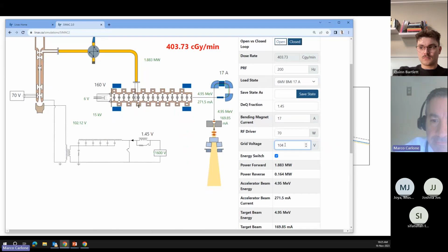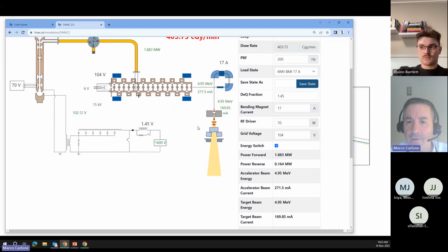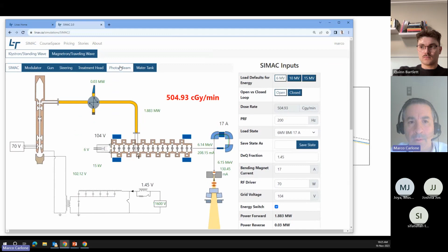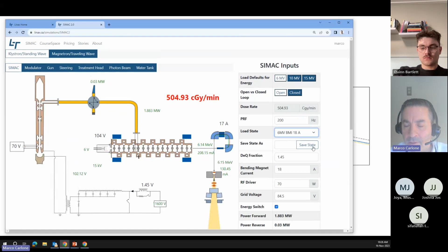Now if I run this, the energy is probably about, if I remember correctly, 6.5 MeV or something like that. So let that run, and then we can look at the effect this has on the profiles, as well as on the depth dose. So it's a little more than 6. On our photon beam screen, our depth dose has changed a little bit, and the profiles have also changed a little bit, but it's difficult to quantify what that is. I'll do the next one. I'll go to 18 amps, which is the highest energy that I've tested, and then I'll run that.